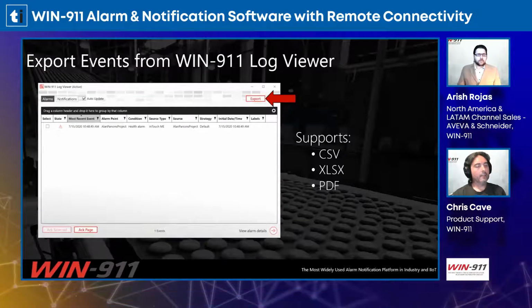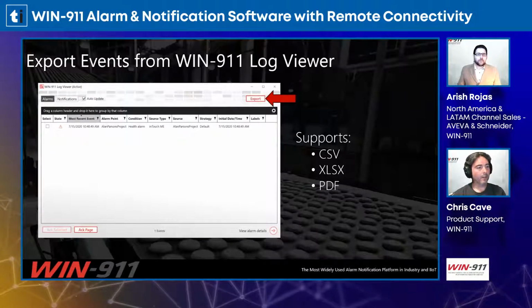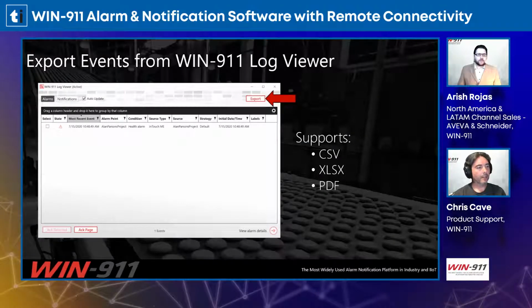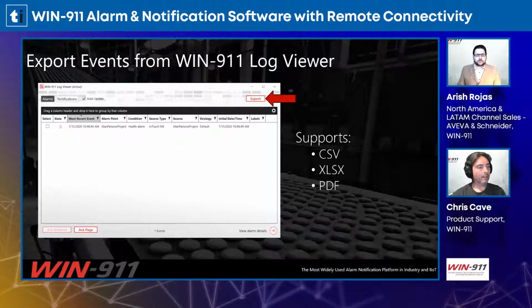This is our bread and butter: Log Viewer, also known as the alarm monitor window. This is where you'll see alarms come in from your SCADA to Win911. You can see what strategy it took, which is the call-out list, the beginning of the call-out list, and what the tag names are.